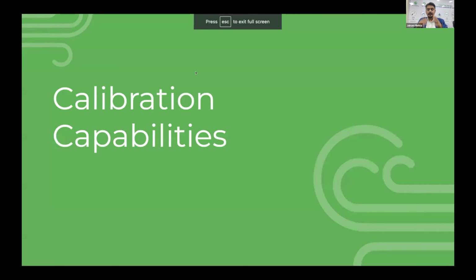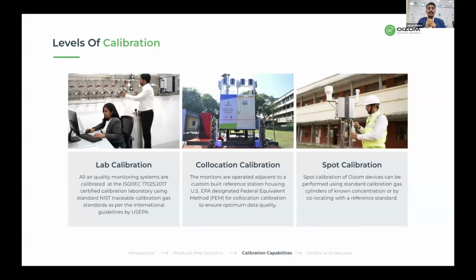Perfect. Now, for any measurement equipment, including a weighing scale, it has to be calibrated regularly, and calibration is very crucial. Every system that is dispatched out of the Oizom facility goes through an extensive 3 levels of calibration. The first one is a factory level calibration, where all the sensors are bump tested to ensure that no kind of anomalies are there in the sensors and the sensors are working perfectly fine.